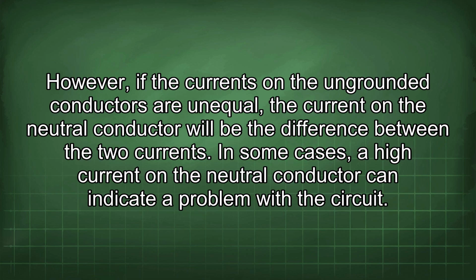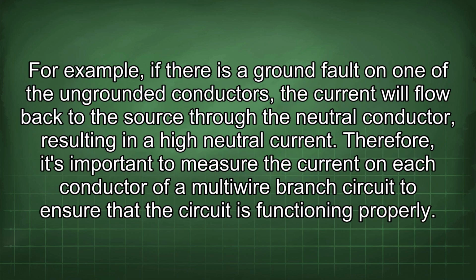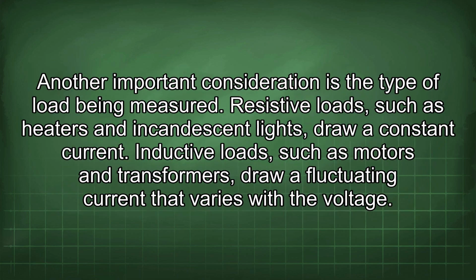between the two currents. In some cases, a high current on the neutral conductor can indicate a problem with the circuit. For example, if there is a ground fault on one of the ungrounded conductors, the current will flow back to the source through the neutral conductor, resulting in a high neutral current. Therefore, it's important to measure the current on each conductor of a multi-wire branch circuit to ensure that the circuit is functioning properly. Another important consideration is the type of load being measured.